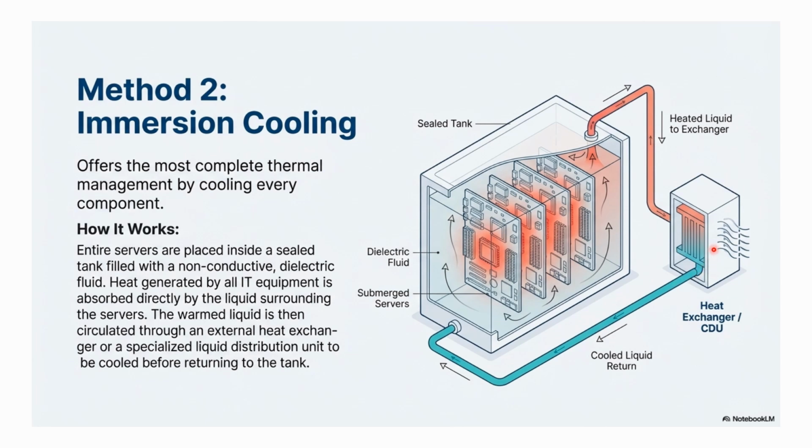Oh, definitely not. It has to be a non-conductive dielectric fluid. Yeah. It won't conduct electricity at all. What's it made of? It can be anything from a kind of mineral oil to highly engineered synthetic fluids that are way more expensive but much better at transferring heat. The heat just gets absorbed by the liquid all around the components.